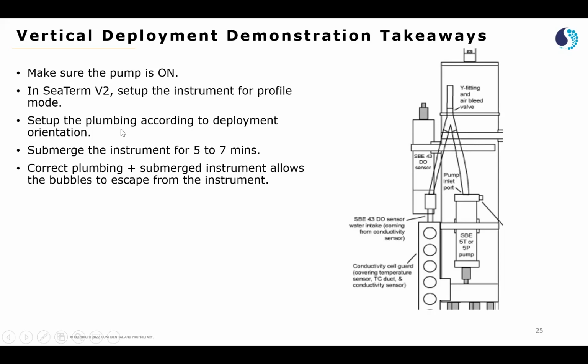It's important to also note that the plumbing is set up according to the deployment. For instance, here I deployed the instrument in vertical orientation, so my Y bleed fitting and air bleed is at the highest point, so that all the bubbles come out of the instrument, and then start deploying.